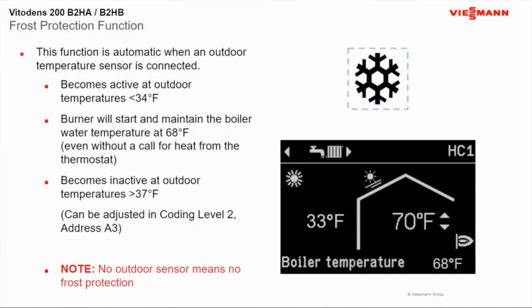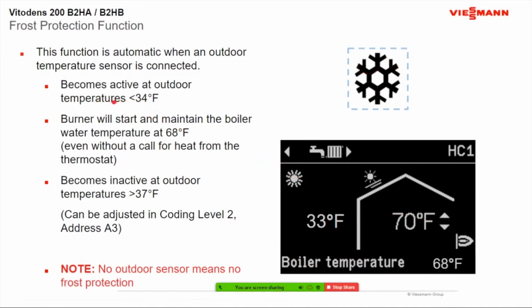And here again, if you do have your outdoor temperature sensor, this is what frost protection will do. It will put a snowflake up here on the screen that looks like this. So once it hits 34 degrees outside, you now know that the boiler will be maintained at 68 degrees. So say your pump fails going out to your system, the boiler will still be maintaining 68 degrees. Say the homeowner calls, I don't have anything running, but my boiler's still running. This is why.